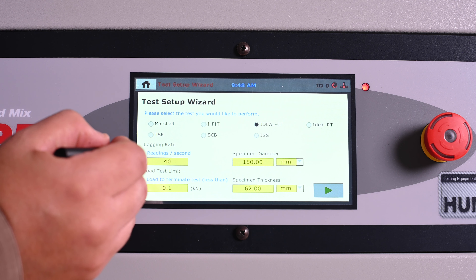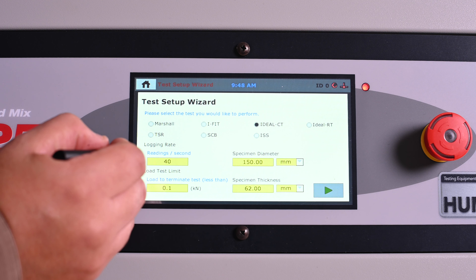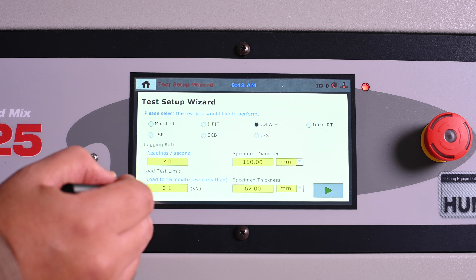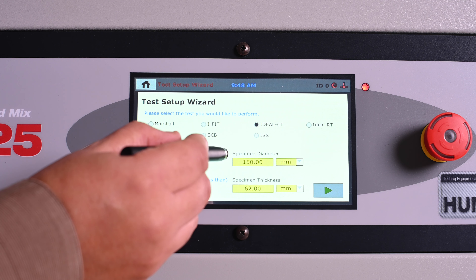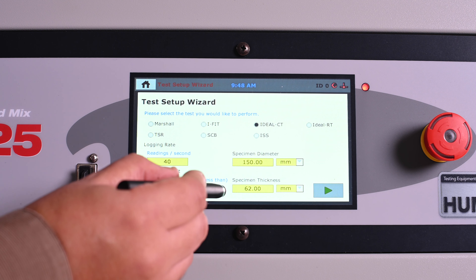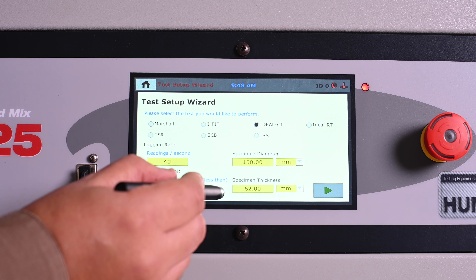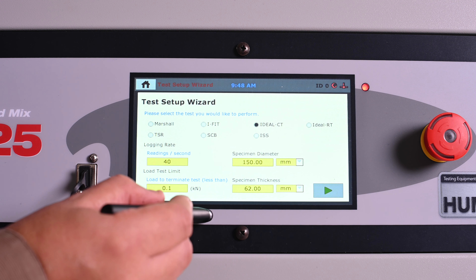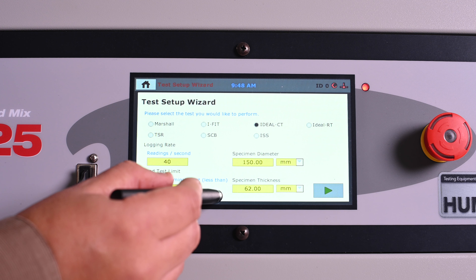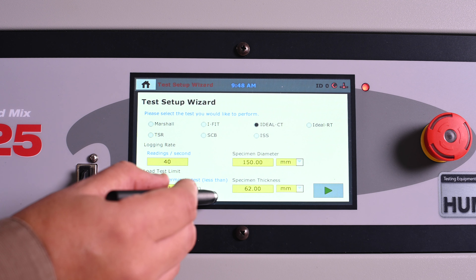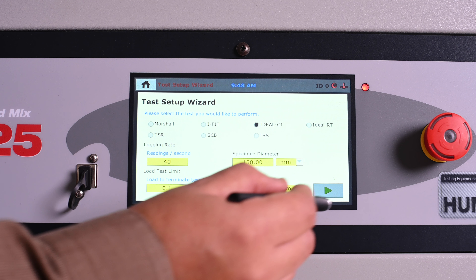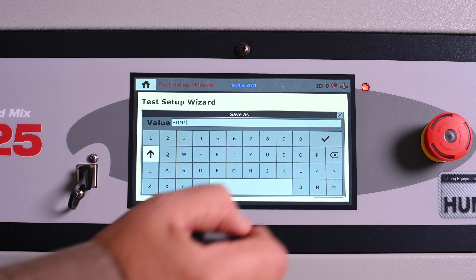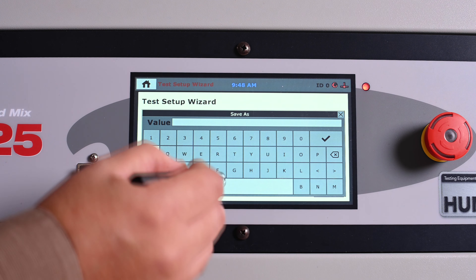The load frame will automatically fill in the standard test parameters for logging rate, load test limit, specimen diameter, and specimen thickness. You will also have the option to change these parameters on this screen. Once you are satisfied with the test parameters, press the green arrow to advance to the next screen.